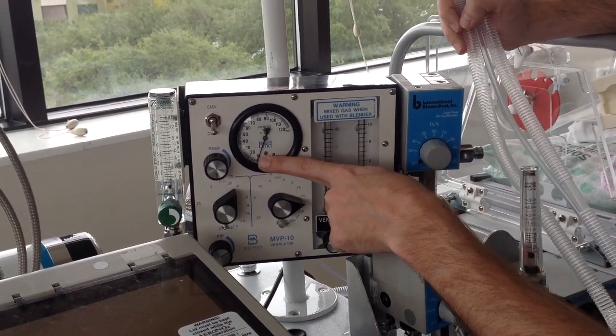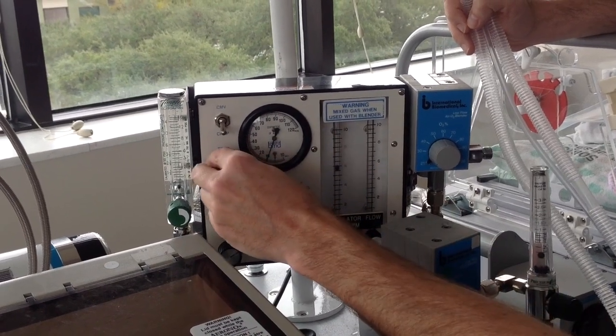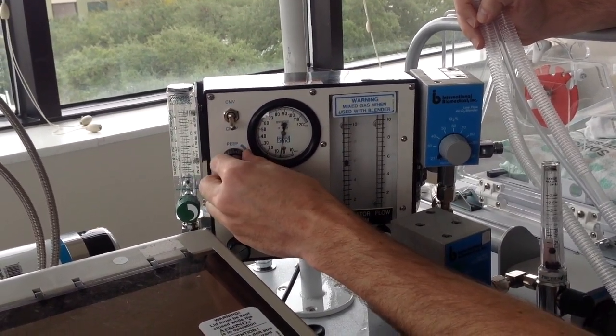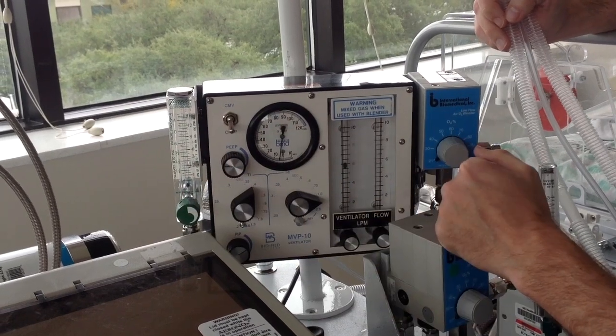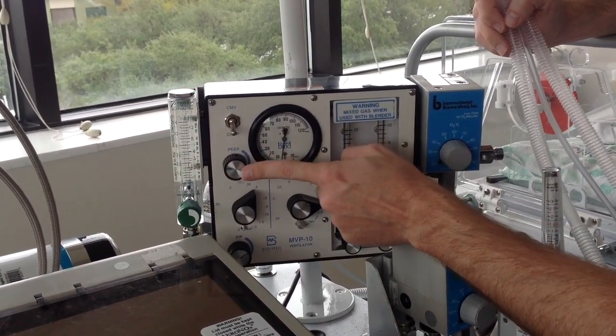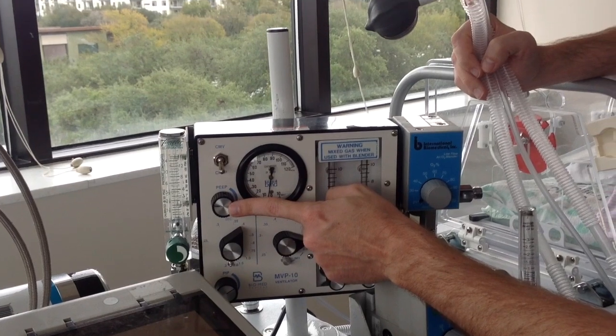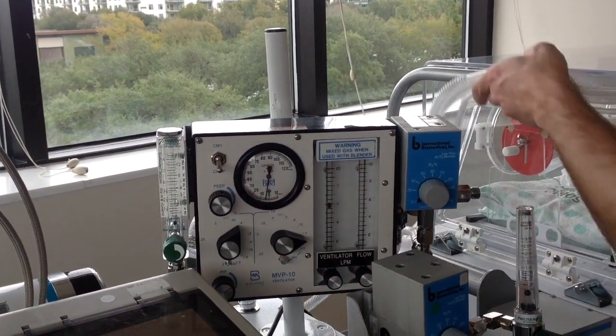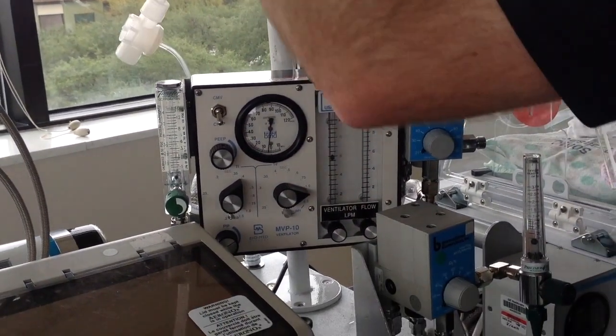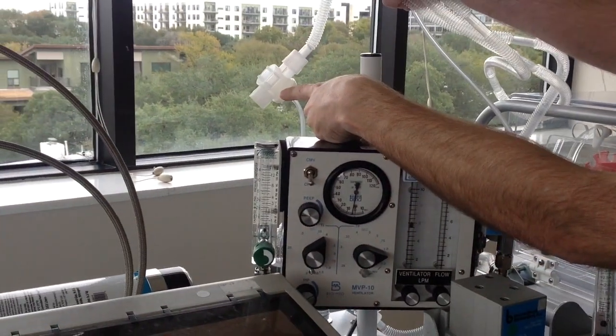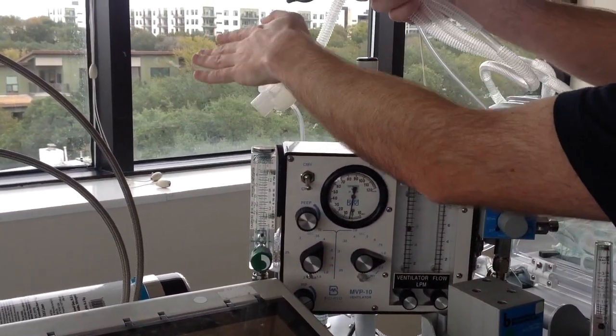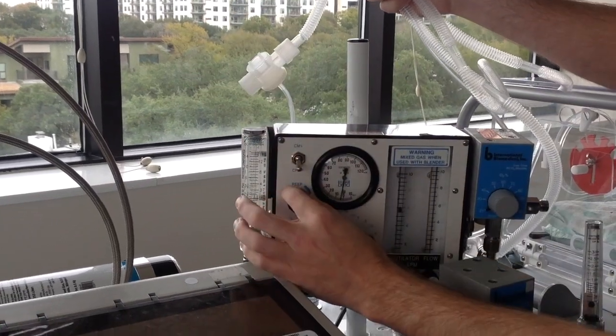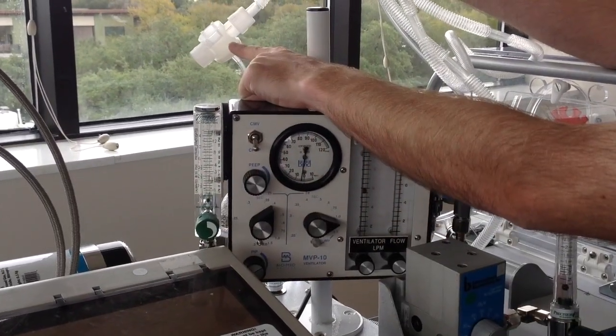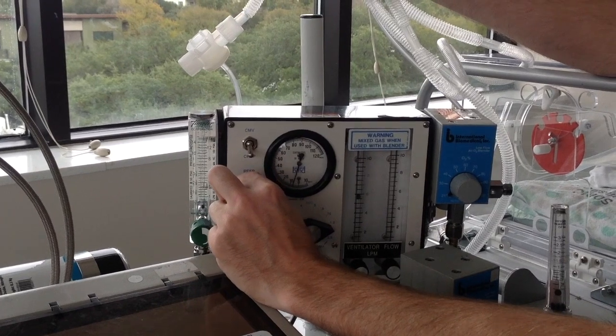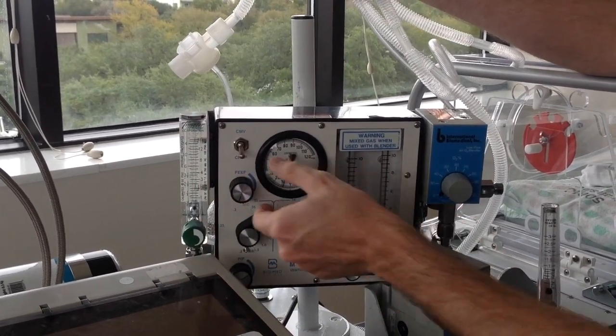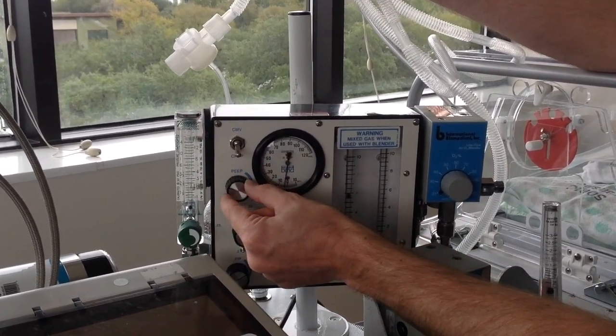So right now our PEEP is reading 10. Say we want to bring that down to 5 or 6 or 4, wherever you want to put it. How I adjust that with the PEEP knob is through essentially this part of the circuit, right? You have exhalation taking place out here, and if I turn this knob, I'm going to be restricting exhalation. If I increase it, I'm going to bring my PEEP up. If I decrease it, I'm going to let more gas out and bring my PEEP down.